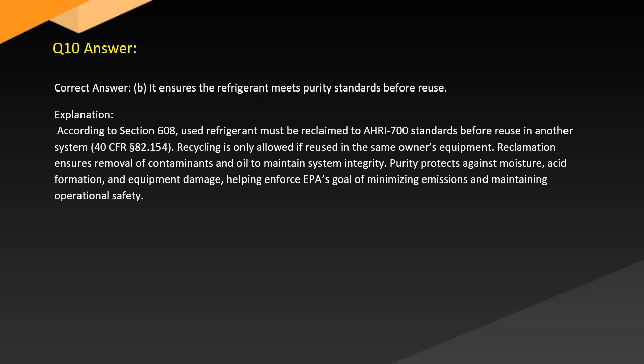Answer. Correct answer: B. It ensures that refrigerant meets purity standards before reuse. Explanation. According to Section 608, used refrigerant must be reclaimed to AHRI 700 standards before reuse in another system, 40 CFR 82.154. Recycling is only allowed if reused in the same owner's equipment. Reclamation ensures removal of contaminants and oil to maintain system integrity, purity against moisture, acid formation, and equipment damage, helping enforce EPA's goal of minimizing emissions and maintaining operational safety.